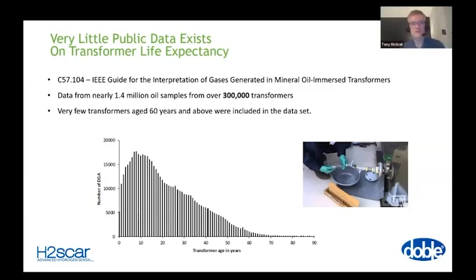Yeah, sure. This is an interesting chart in that it doesn't tell you anything about how many have failed. It only tells you the age of a unit in service. It doesn't tell you how long it lasted after that. It doesn't tell you if we've had 100 samples taken from one transformer. It just gives an indication that there are fewer samples from older transformers, therefore older transformers are less likely to occur.